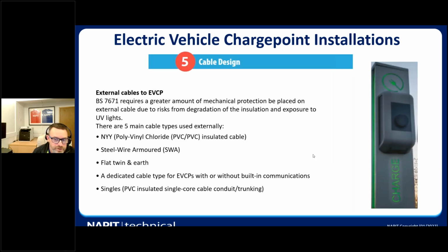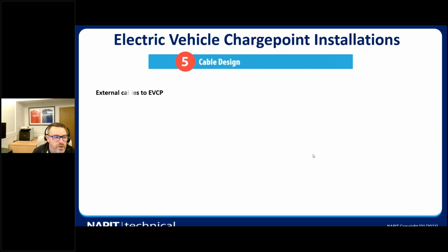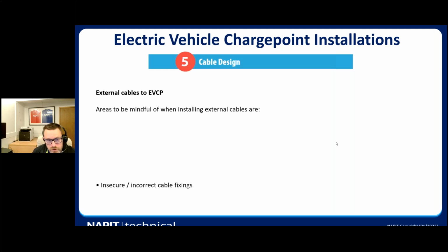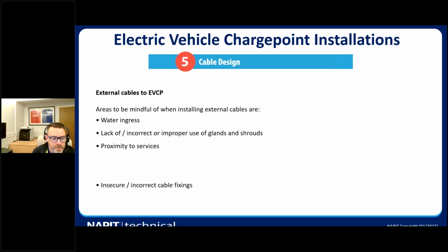And it's just an example of an external charge point. External cables to EVCP. So, mindful when we're installing external cables are water ingress, lack of or incorrect use of glands and shrouds, proximity to service cables, bending too tight a radius of the bend, and poor choice of cabling routes. There is some access to cables we've got to be mindful of, where people can be exiting buildings, things like that.